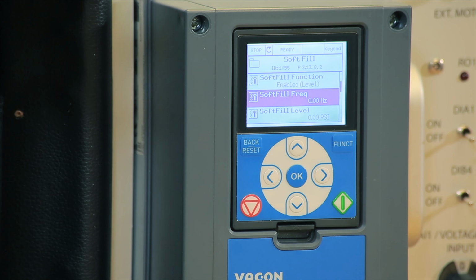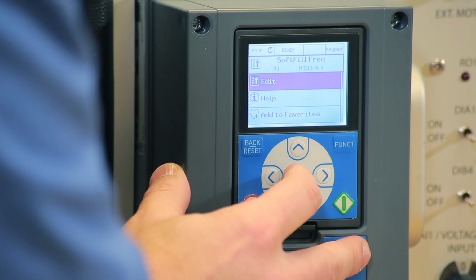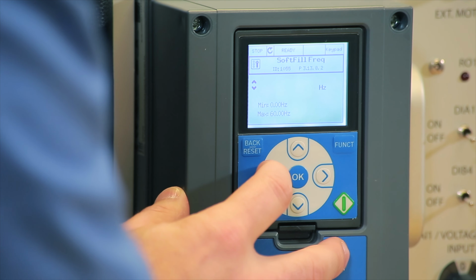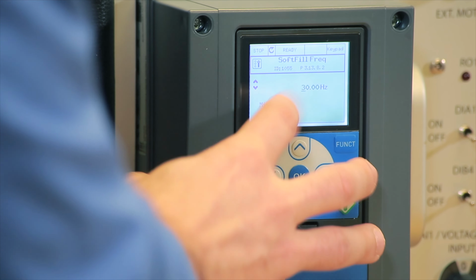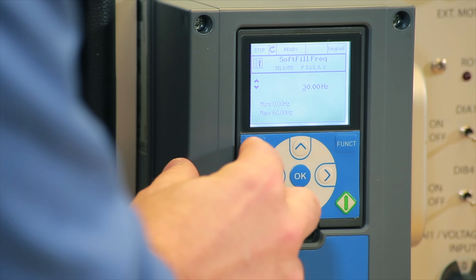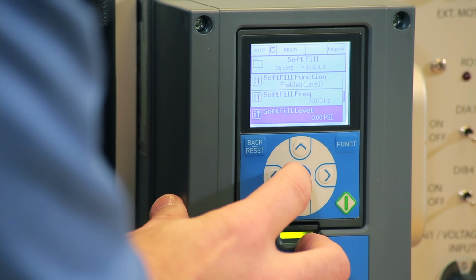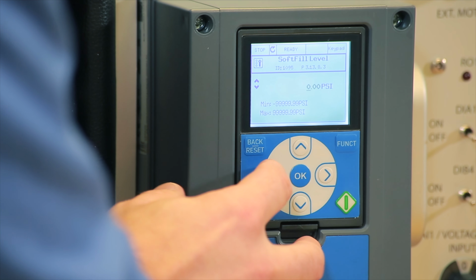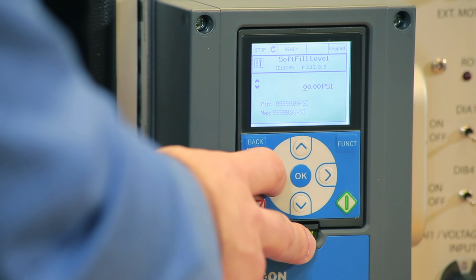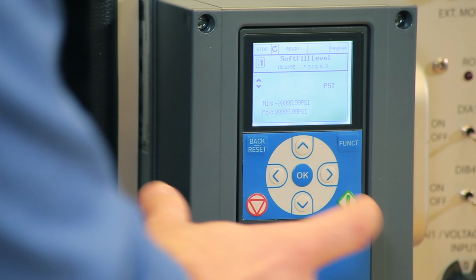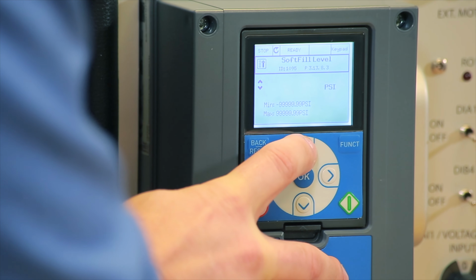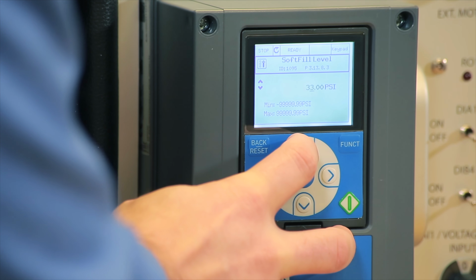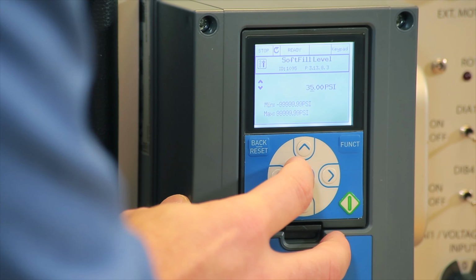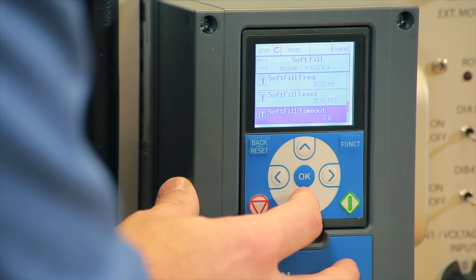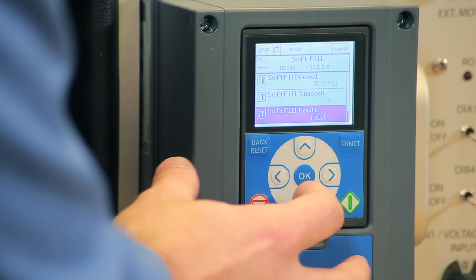We're going to go back once. Now when we are soft filling the pipe, what frequency should we run the drive at so we prevent water hammer? We're going to go in here and edit, and say let's run at 30 hertz, the pump minimum speed, until the pressure is, we're going to edit this, and wake up level was 60, so we could say until 35 psi, just an example here. So 30, and 35 psi, and this is it. We're not going to do the timeout, so if there is any fault, the drive will fault.